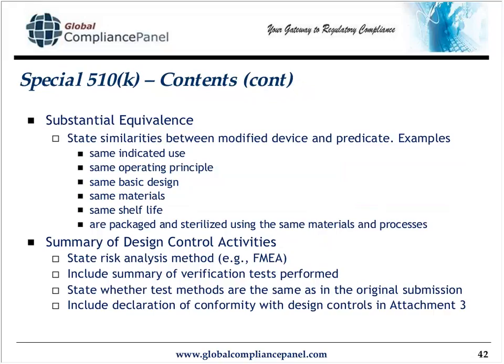In the substantial equivalence section, similarities and differences between the two devices, I like to include a dozen characteristics, and when only 2 of them have changed, it really illustrates to the reviewer how little has changed between the 2 devices. I find that's much more effective than merely listing those 2 things that have changed. I like to include what has remained the same as well.